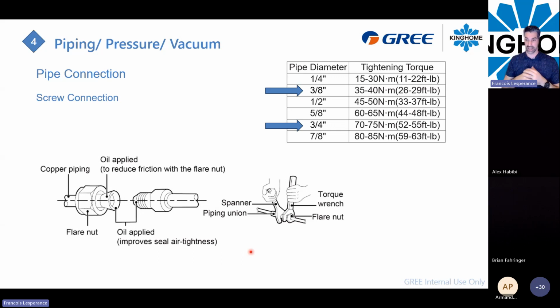That's a natural thing. It will happen, but if you can, in your piping work, make some bends and turns, that will reduce the pressure on the flare connection. So make sure you don't just throw the piping in straight ahead and add some clips so it's too tight against the wall or in the ceiling. Make sure the piping can move freely to take that expansion.